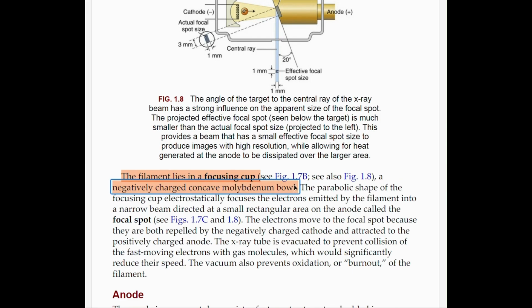So first, the cathode consists of the filament and the focusing cup. The filament lies inside the focusing cup. The focusing cup is nothing but a negatively charged concave molybdenum bowl. The parabolic shape of the focusing cup electrostatically focuses the electrons emitted by the filament into a narrow beam directed at a small rectangular area on the anode called the focal spot. So what is the work of the focusing cup? It focuses the electrons that are emitted by the filament. In the filament we have 1% thorium, so that more electrons are emitted.